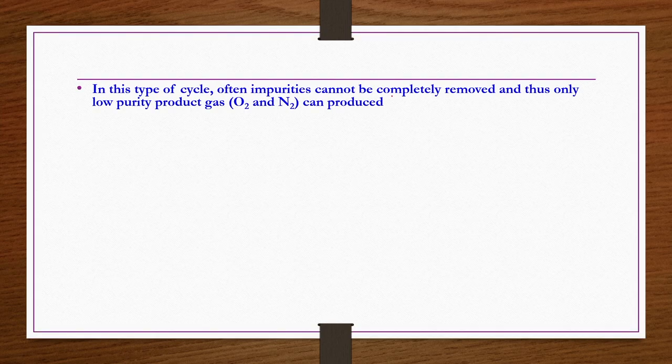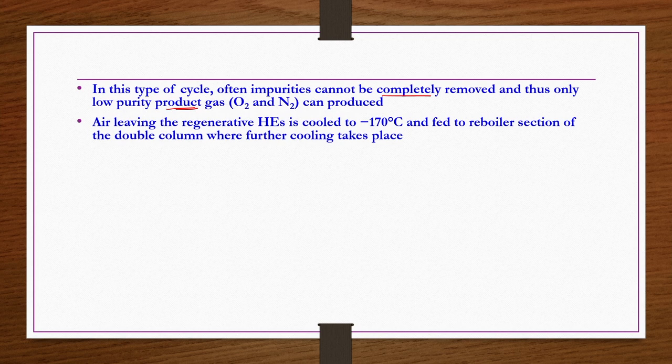In this type of cycle, impurities cannot be removed completely, so you can produce low purity product gas — O2, N2, or both. Air leaving the regenerative heat exchangers is cooled to minus 170 degrees centigrade and fed to the reboiler section of the double column where further cooling takes place. What is this double column? Two distillation columns, one mounted onto the other.